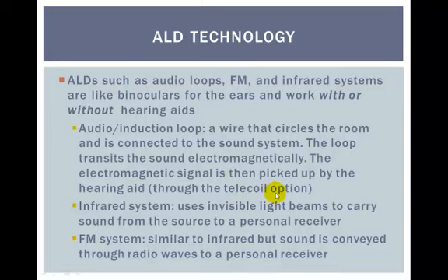Remember when we talked about features with hearing aids, and we talked about a telecoil option, where a hearing aid may have an option that either the person pushes the button or it happens automatically, that when a telephone, and we're talking about a landline versus a cell phone, gets close enough to the hearing aid, it can pick up that electromagnetic signal of the phone and instantly switches into telecoil mode to amplify the voice on the phone, and only the voice on the phone.